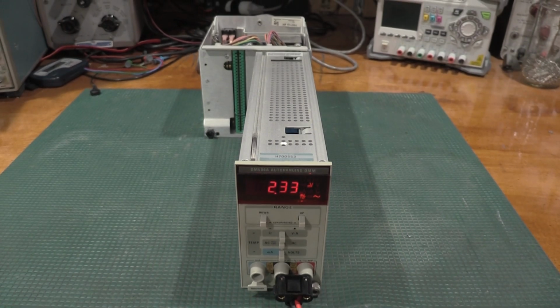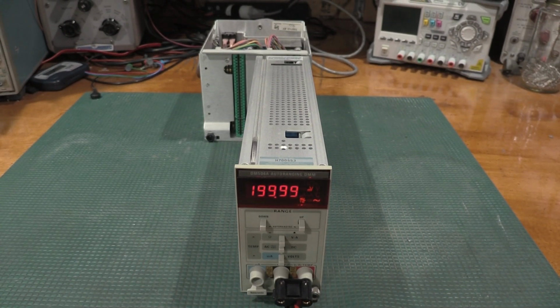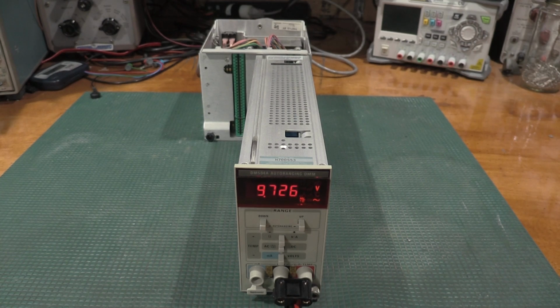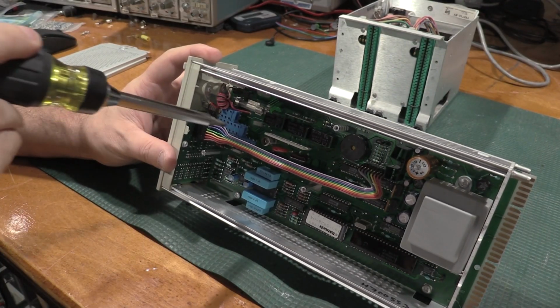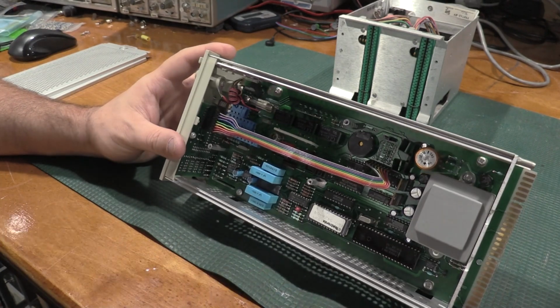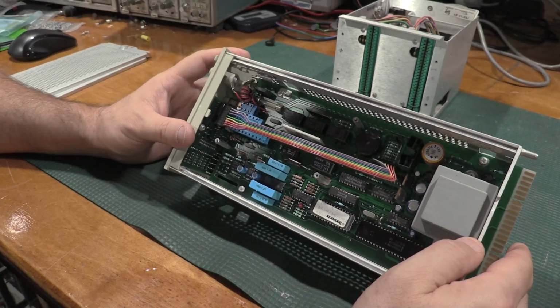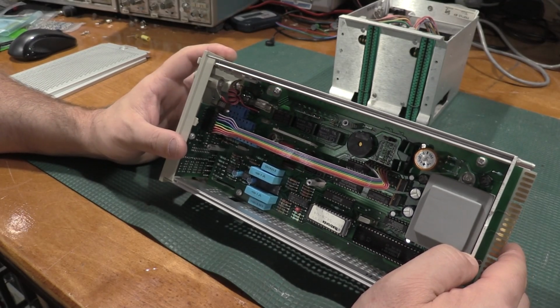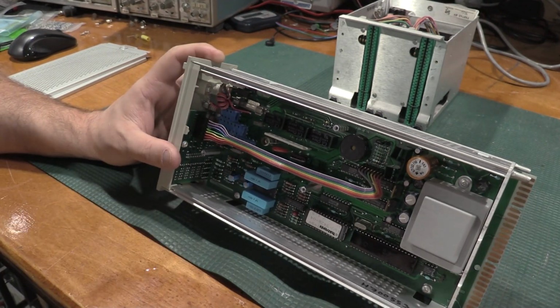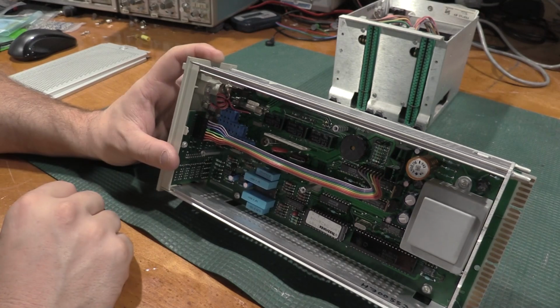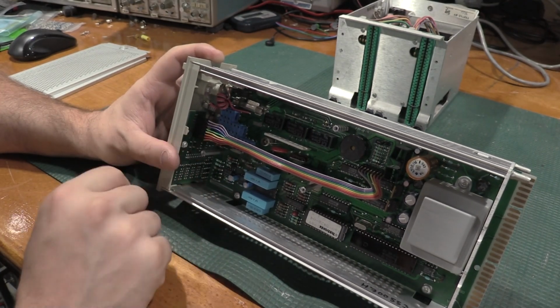Okay, so we have 9.99 volts coming out of the calibrator. I'm going to hit this, let it do its thing. So that's reading way off and climbing, so I have a sneaking suspicion I know what's going on. So let's pull this cap and check it for leakage. Okay, with the covers pulled off, this is our capacitor that we are interested in taking a look at. It's a trimmer cap, and it's rated for 750 volts, but it needs to see 1,000. So most of the front end, well, these two caps right here, the red one and the glass trimmer, do see the entire voltage applied to the front end. So this one right here tends to be the sore spot. So we're going to pull him out, check him for leakage.